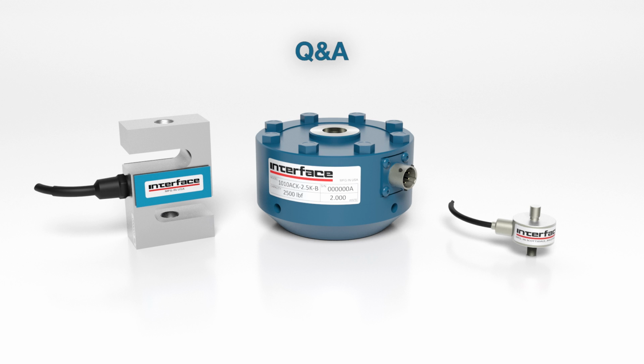Okay, next question. Where is the most appropriate place to ground the shield or drain wire? Well, typically that's going to carry through to where you're grounding your instrumentation as well. Don't typically want to have that connected on the load cell side as well. So it's really going to depend somewhat on your actual installation. Sometimes just going to the case of the instrument or to the same ground your instrument's using is sufficient, or if you actually wanted to go to a ground stake, you could do that as well.